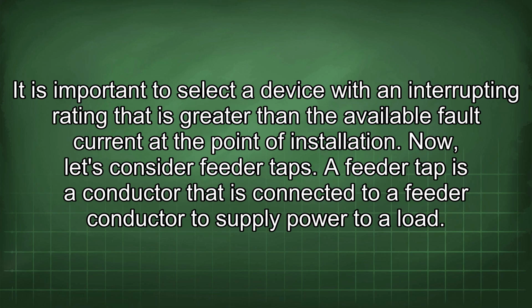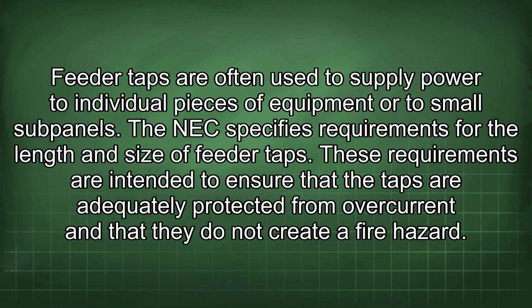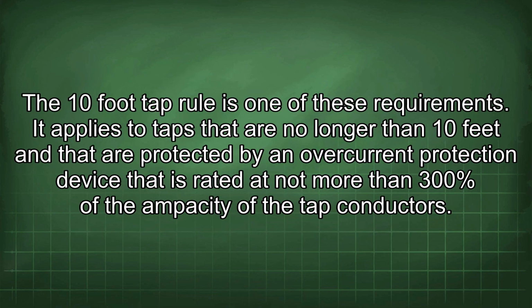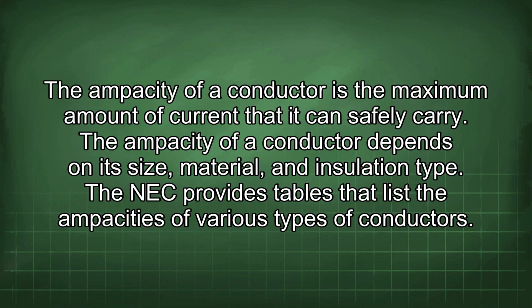A feeder tap is a conductor that is connected to a feeder conductor to supply power to a load. Feeder taps are often used to supply power to individual pieces of equipment or to small subpanels. The NEC specifies requirements for the length and size of feeder taps. These requirements are intended to ensure that the taps are adequately protected from overcurrent and that they do not create a fire hazard. The 10-foot tap rule is one of these requirements. It applies to taps that are no longer than 10 feet and that are protected by an overcurrent protection device that is rated at not more than 300% of the ampacity of the tap conductors. The ampacity of a conductor is the maximum amount of current that it can safely carry.